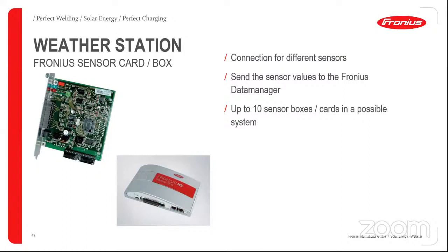Good. We also have this weather station where we can connect different sensors. We do have two different options to connect the weather station. One can be with a card and another one with a box. The difference is where you want to put the sensor. So for example, if the sensors are very close to the inverter, less than 20 meters, you only need to use this card and it can be put inside the inverter. But if the sensors are going to be a little bit farther than 20 meters, you need the box.